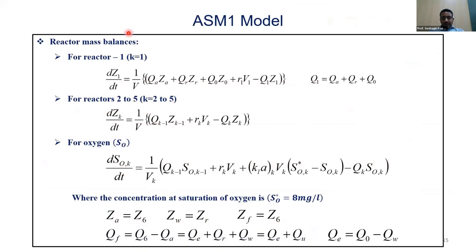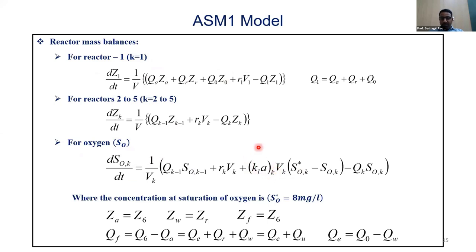The mathematical model, according to the International Water Association task group, ASM-1 (Activated Sludge Model 1), treats all reactors as CSTRs — continuous stirred tank reactors — and the model is developed based on first principles. For writing the oxygen model, we account for the external air supply represented by the mass transfer coefficient KLA, and the saturation value of dissolved oxygen concentration, which is recommended as 8 mg/L in wastewater environments.